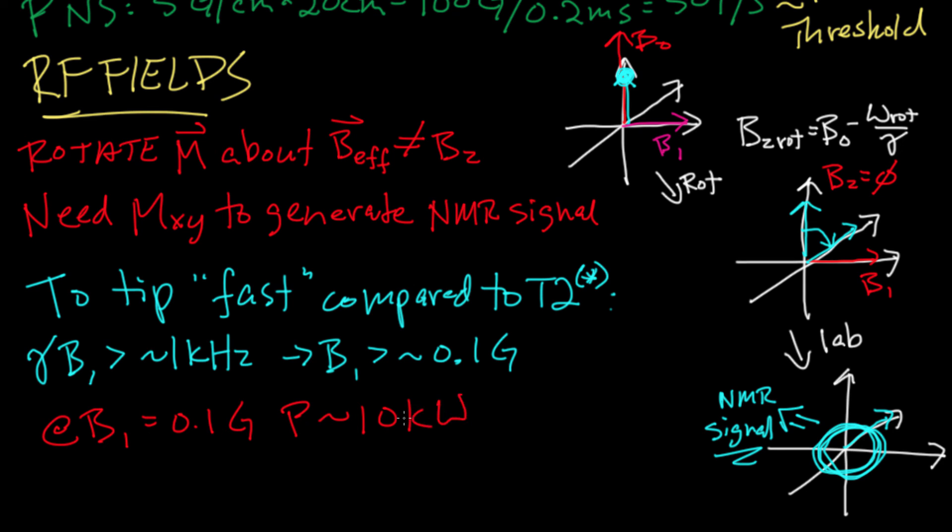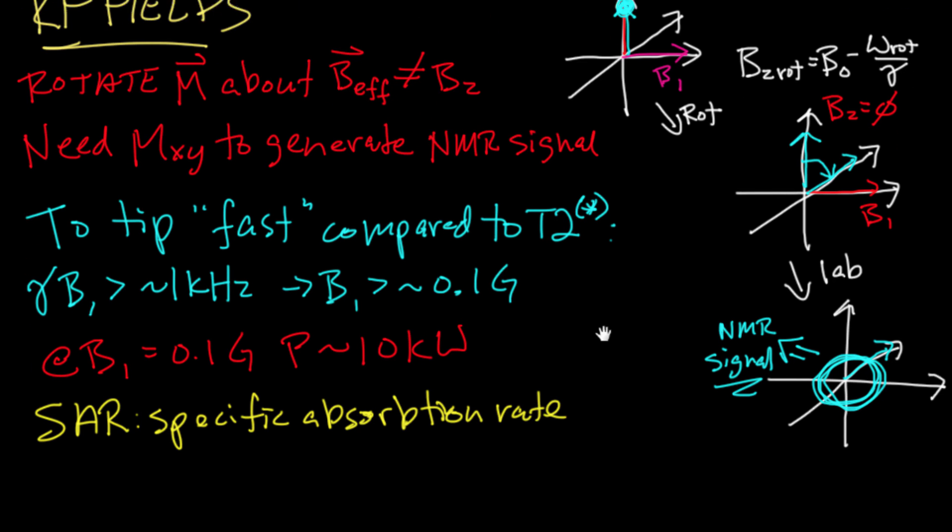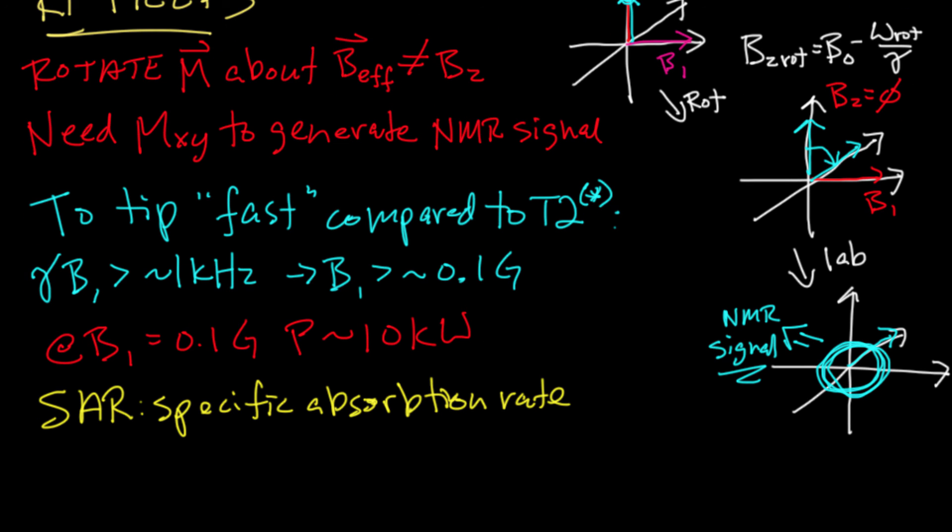That discussion is beyond the scope of this introduction, and so we'll jump to the answer. And that is that to produce a B1 field of about 0.1 Gauss in a human body, you need about 10 kilowatts of RF power. Now the primary limitation to how much power you can apply is the fact that some of that power is actually deposited in the body and converted into heat. And that absorption of power is characterized by something called the specific absorption rate. The FDA regulates SAR, and fortunately the power that's required to perform MRI effectively at the duty cycles that are required for MRI pulse sequences results in temperature rises in the body that are much, much less than 1 degree.